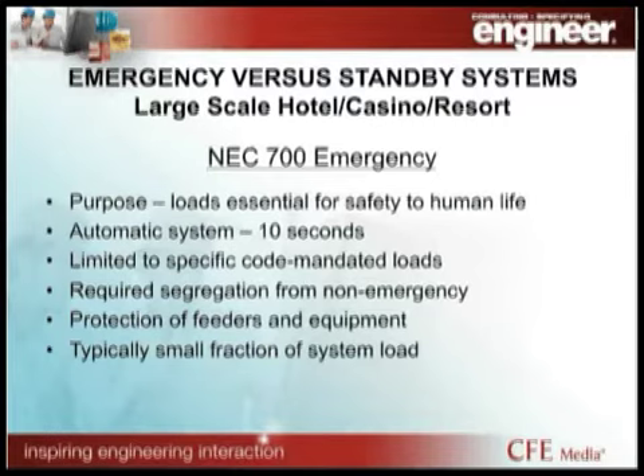And then one of the things that for a bigger system becomes a bit of an issue is that it's typically a very small fraction of your load. Most of the designs that we do, we're taking either 12-470, 11 kV if it's international, or 22 kV, and we're distributing around the property both emergency, your legally required, and your optional standby, or business critical, as they call it in Asia. So when you've got such a small fraction of a load on a system that is really designed for more bulk distribution, it becomes interesting as to how you have to address that. One of the things that they did in the Las Vegas market a long time ago is they actually allow us at the 15 kV level to combine emergency and legally required into one system because it's more practical.